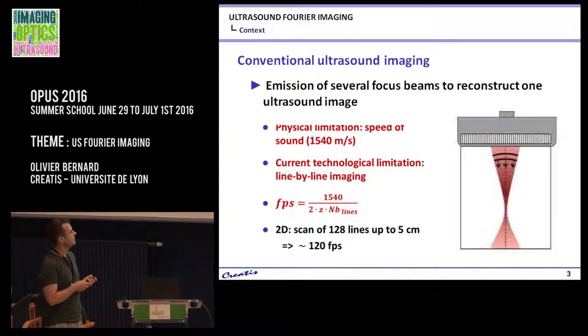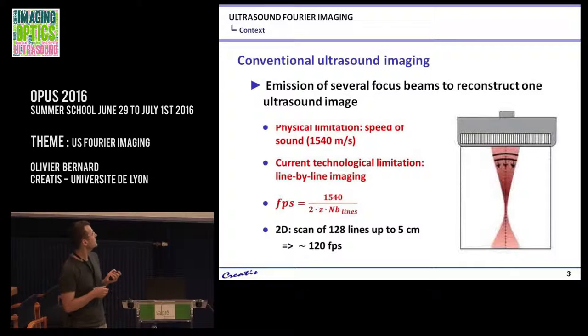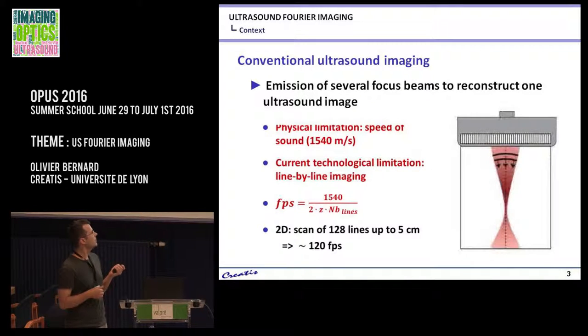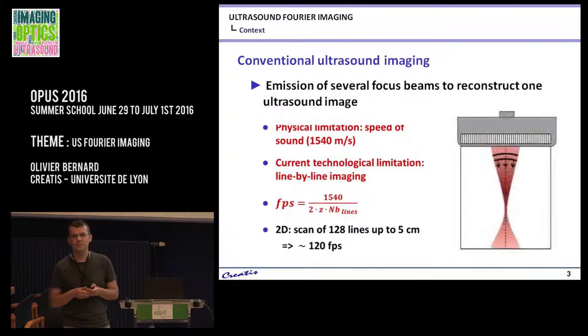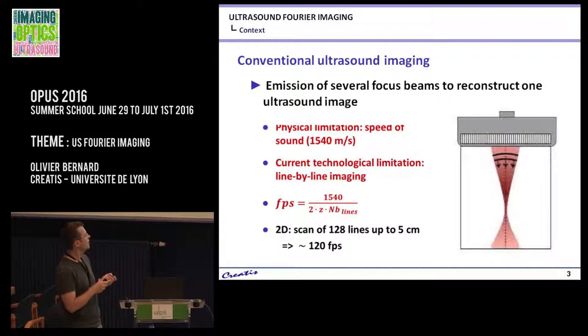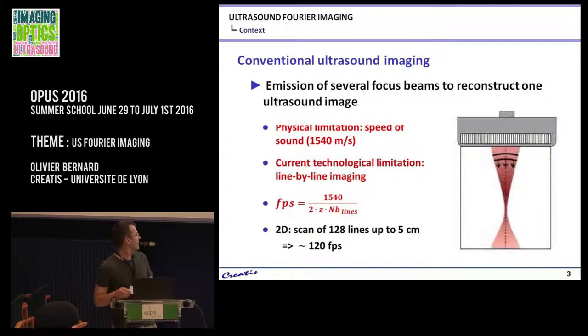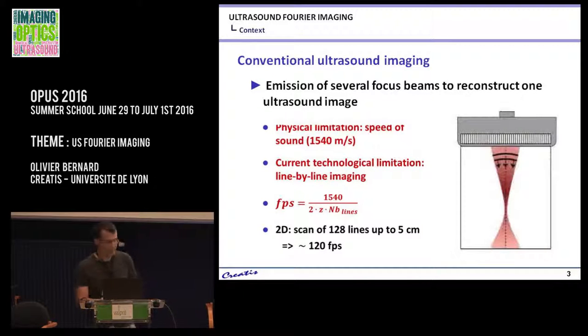Very simply, you have this equation. For example, if you consider that C, which is the speed of sound, is this value, then since you have to wait for your wave to come back before firing the other one, this is the equation. It depends on Z, which is the depth you want to image, and the number of lines that you're going to record. So typically, if you want to image something at 5 centimeters, you want to get up to 120 frames per second.